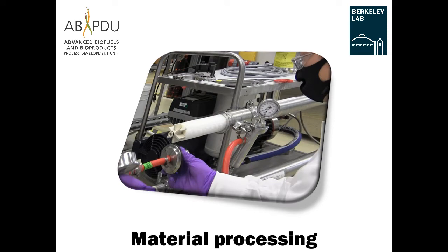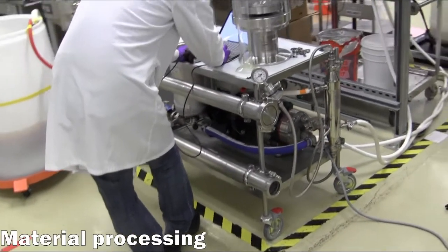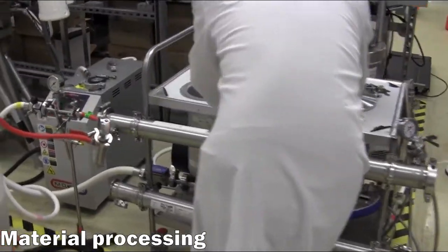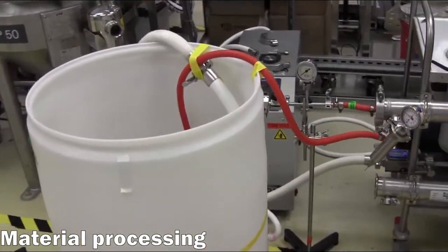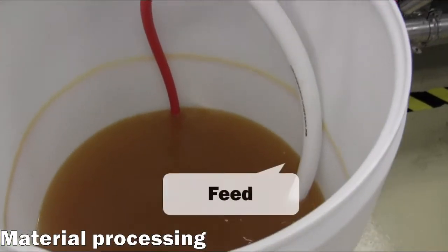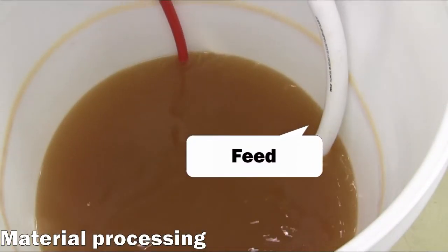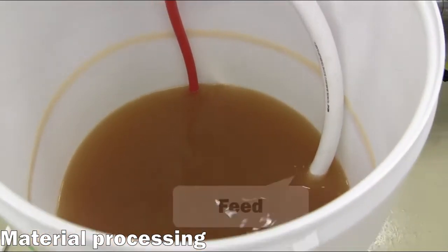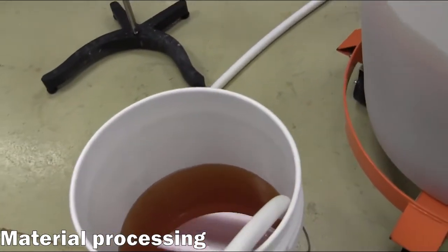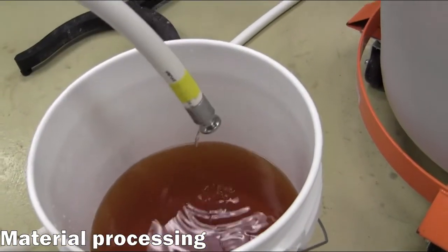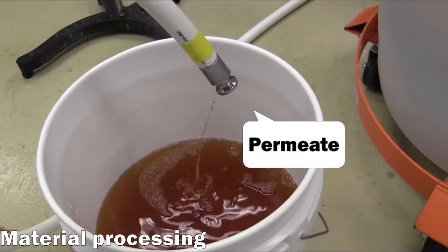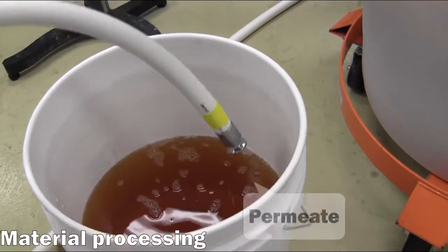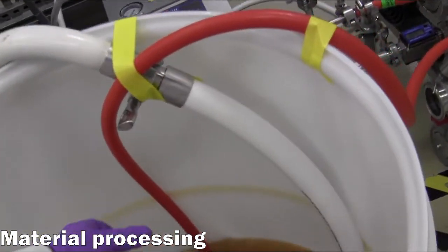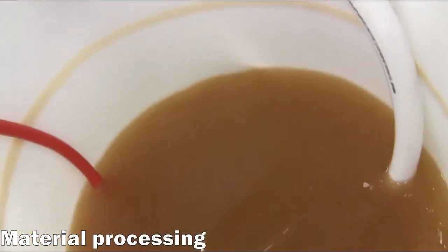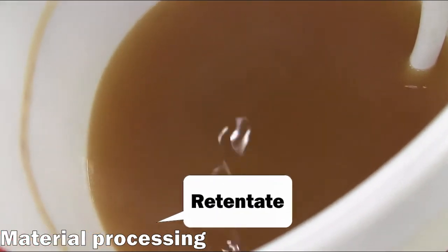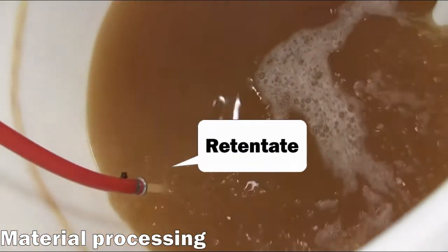Material processing. Now that the membrane performance has been validated, the filtration of the processed material may begin. The feed hose is placed in the holding vessel containing the input material, drawing material into the pump. The permeate hose is fed to a different collection vessel. The retentate hose is also placed in the vessel of input material, allowing the recirculation of unfiltered crossflow.